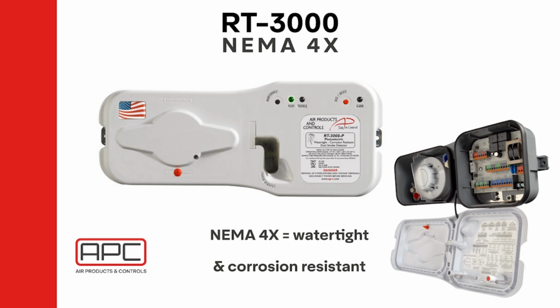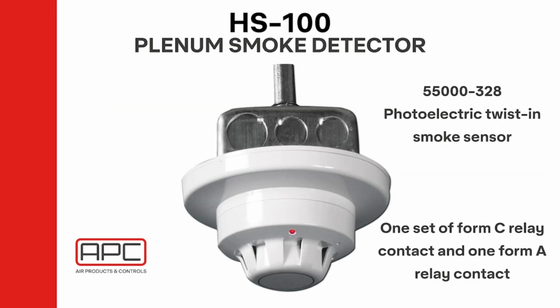The RT3000 also features 2 Form C relay, allowing the detector to alarm, close dampers, and other functions based on the application. The HS100 series is a low to no flow special applications duct smoke detector. It is designed for applications where standard duct smoke detectors cannot be used. Air shafts, plenum spaces, and applications with no air velocity are typical applications for this unit.